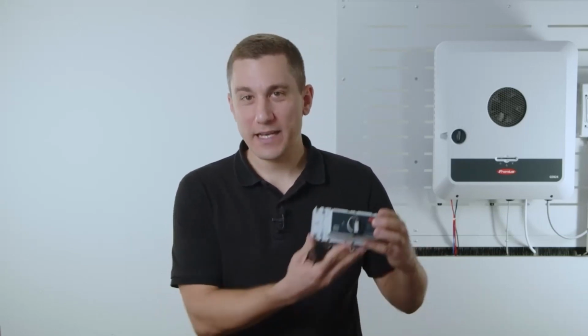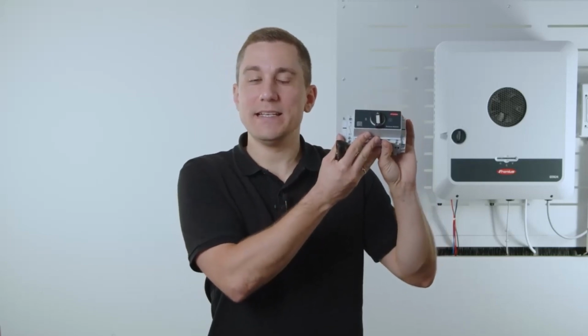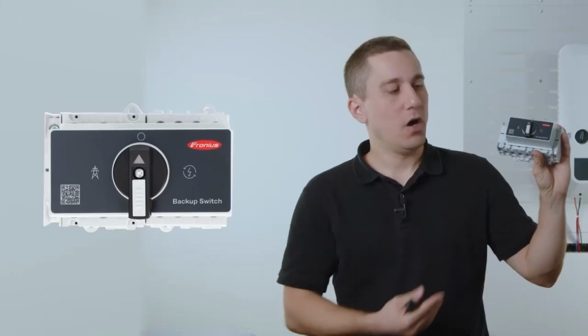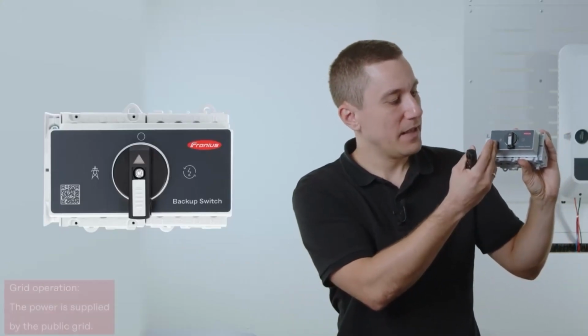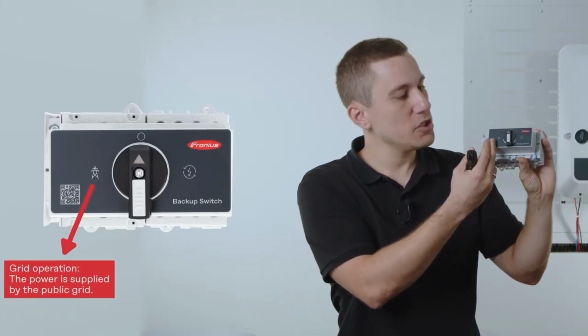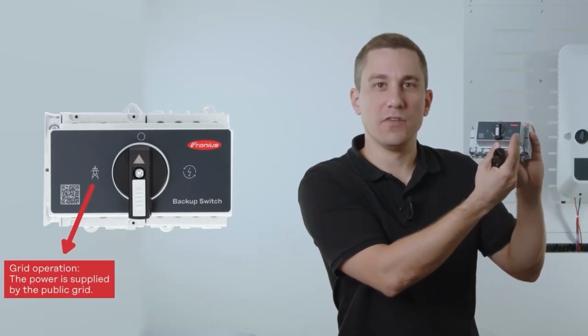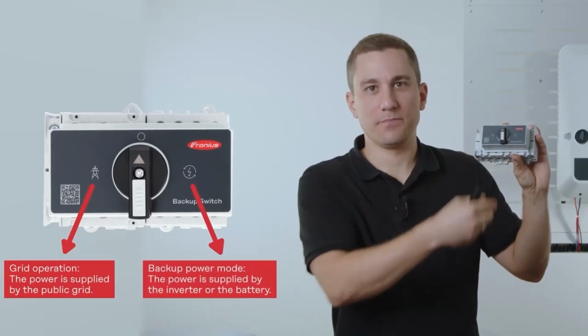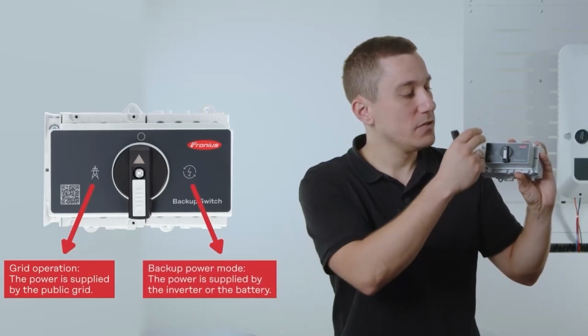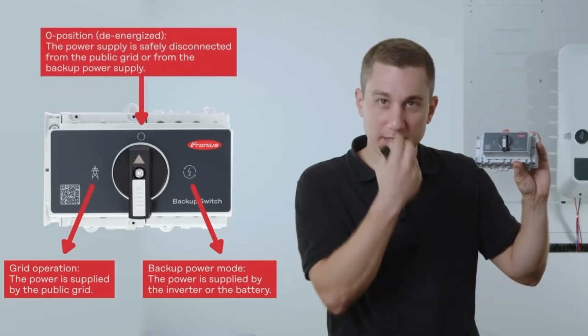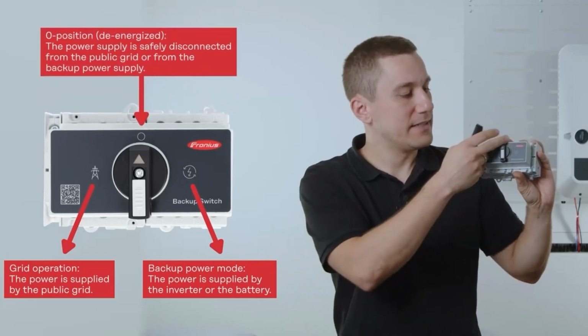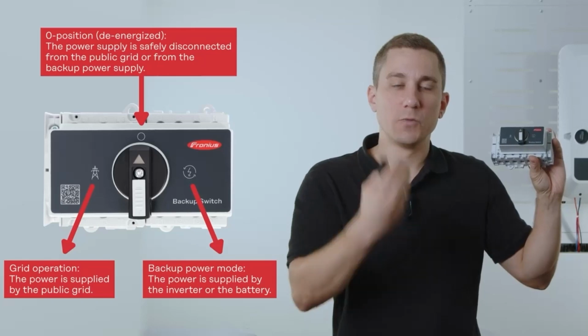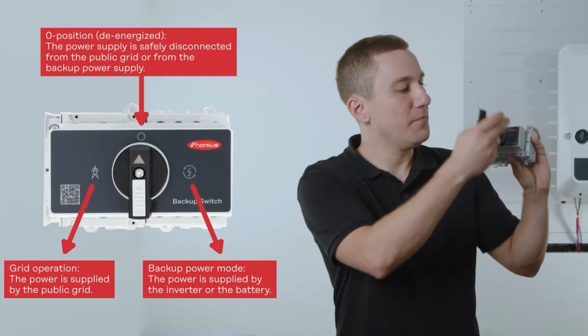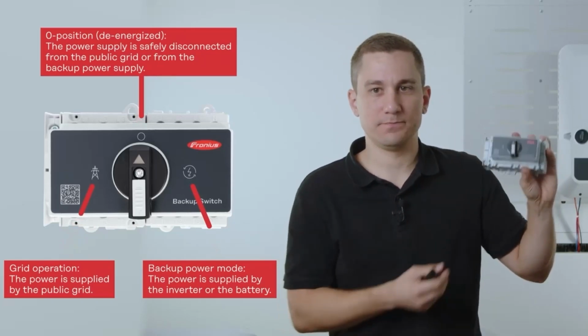With the new Fronius backup switch, you now have the possibility, very easily and compactly, to switch over a full household with three-phase power. On the one hand side, we have the grid parallel position, and on the other hand side, you can switch over to backup position manually. In this case, you are going over the zero position that makes sure that the inverter is switched off and will power up again in the backup position.